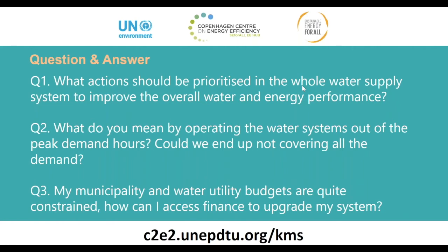So the power utilities are interested in everyone working out of the peak hours to reduce the grid constraints. If the tariff acknowledges it through a variable electricity price, we can always take advantage of it by pumping fresh water into existing storage or reservoirs out of the peak hours, for example, during the night when the electricity is cheaper, and releasing this water when needed.